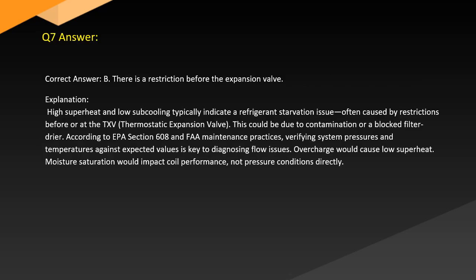Answer. Correct answer B. There is a restriction before the expansion valve. Explanation. High superheat and low subcooling typically indicate a refrigerant starvation issue, often caused by restrictions before or at the TXV, thermostatic expansion valve. This could be due to contamination or a blocked filter dryer. According to EPA Section 608 and FAA maintenance practices, verifying system pressures and temperatures against expected values is key to diagnosing flow issues. Overcharge would cause low superheat. Moisture saturation would impact coil performance, not pressure conditions directly.